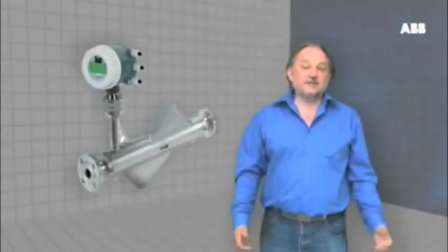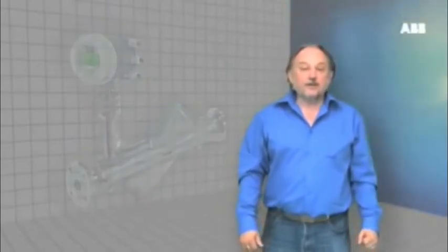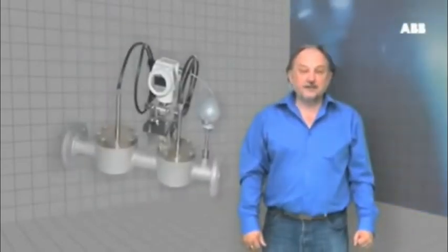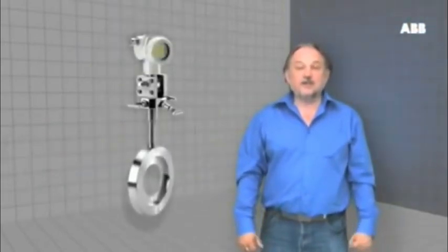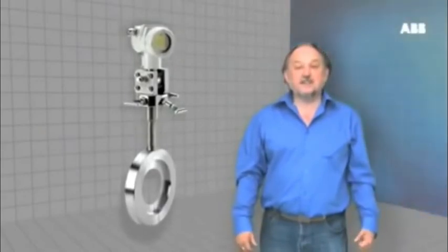For liquid mass flow measurements, especially where variations in product density are common and the product is priced by weight, Coriolis meters should always be considered. Their high accuracy and repeatability means excellent cost savings, and because product density can be measured, the quality of the product or even its identity can be assessed.